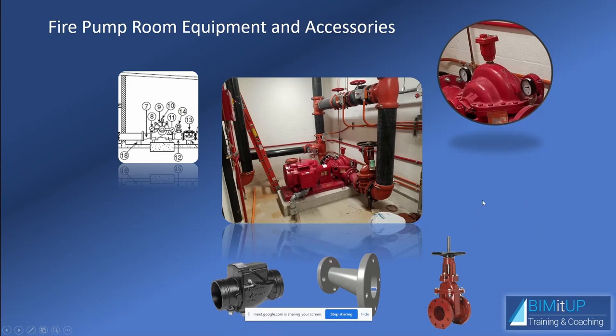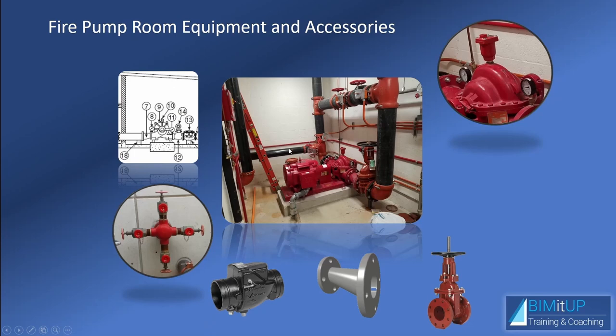So we're discussing some of the components of a fire pump room. We have here also at the discharge of your pump, you always need a check valve to prevent the high pressure water to go back, of course. And then you also have a test header in the outside wall, which will have one fire hose valve every 250 GPM typically. We'll look into that a little bit later.